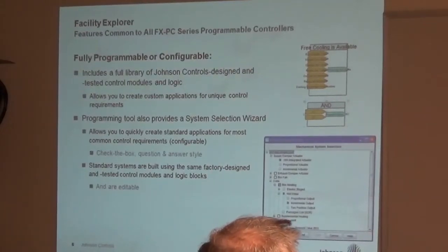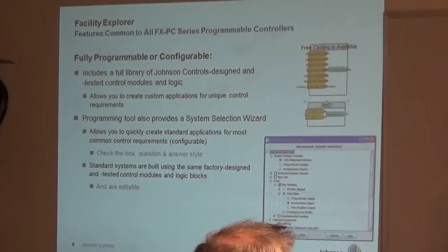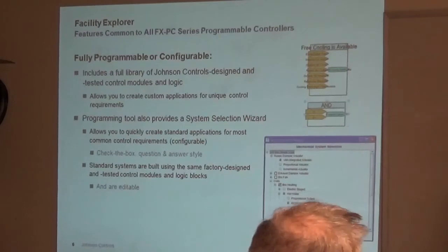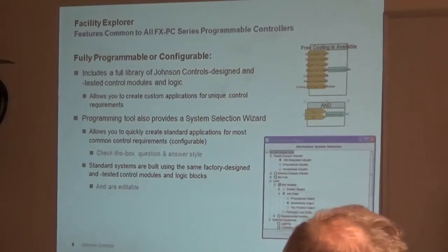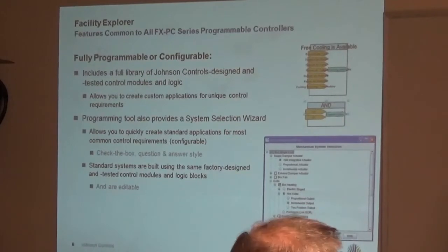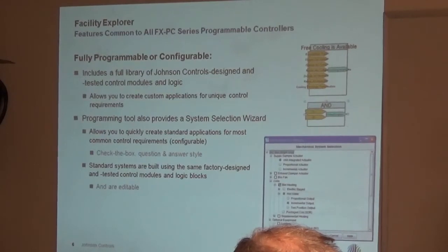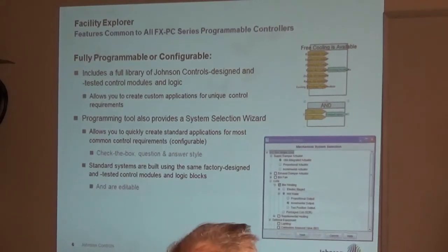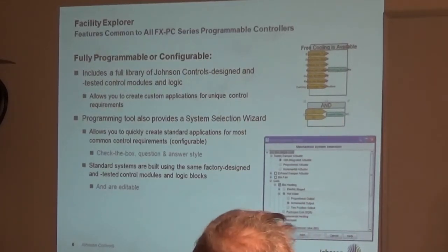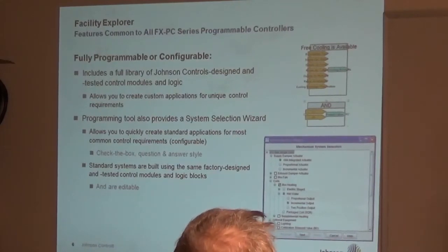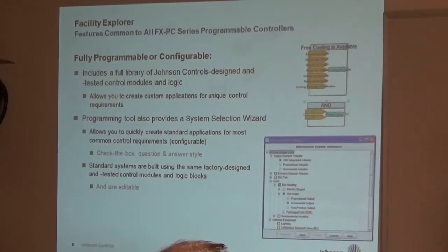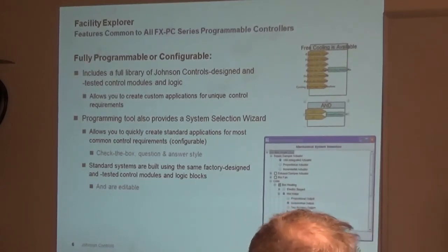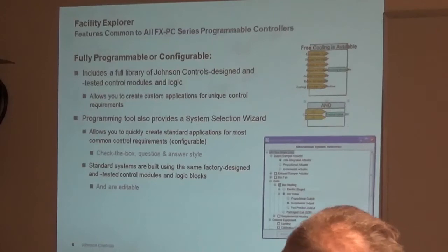Yeah, one of the big problems that I've found in this tree is that you get into more of a configurable, bigger system, with pumps and everything else. They don't ask you the question, like the old Metasys one. HVAC Pro? Yeah. You could have the biggest program and throw it in the AHU and it would work by default. It may not work right, but it would work. No matter what you did, it would work. You can't do that with this.